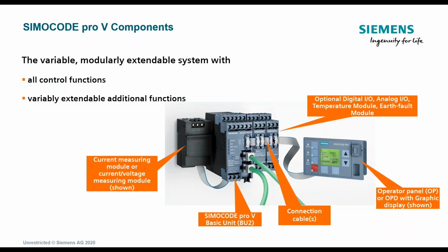This could tell you how long the SIMOCODE's been energized, aka the motor bucket's been turned on, versus how long the motor's been running. So there's some key performance indicators. This could also tell you all the faults that go on within the SIMOCODE. And there are some configurable faults that you can do for your own specific processes. And I'm going to show some of that to you today. Notice that this operator panel also has some push buttons on its side, so this can be your local HOA at the motor control center bucket or at the door of your motor control panel.